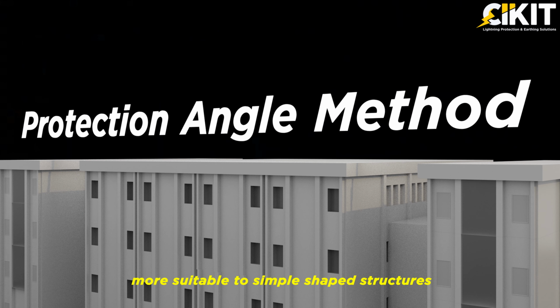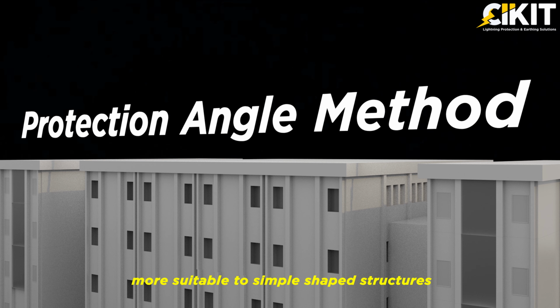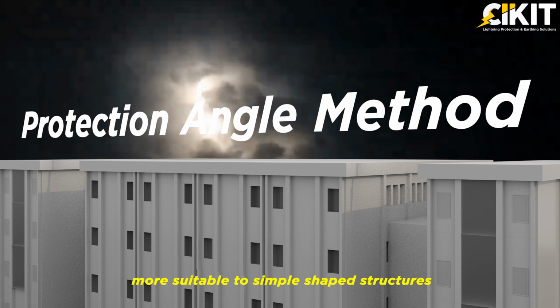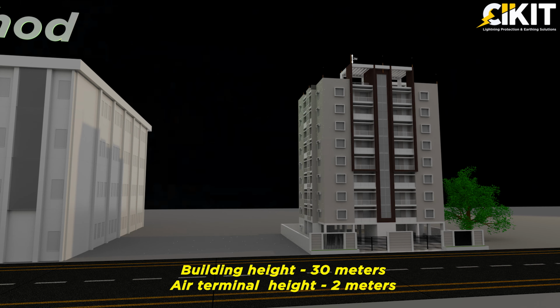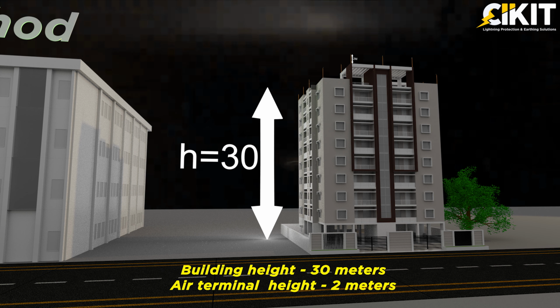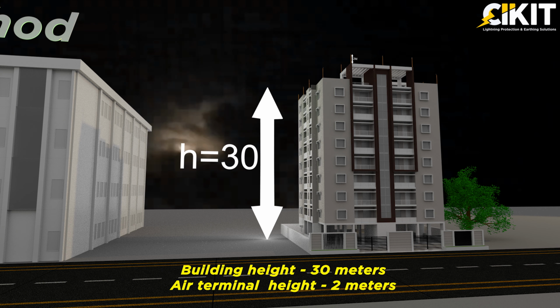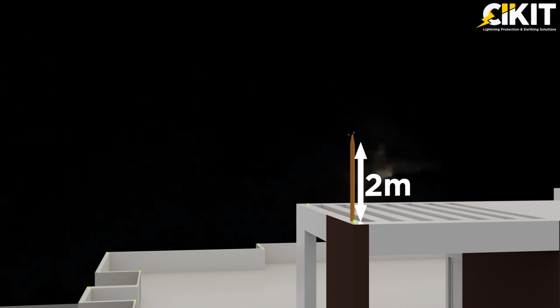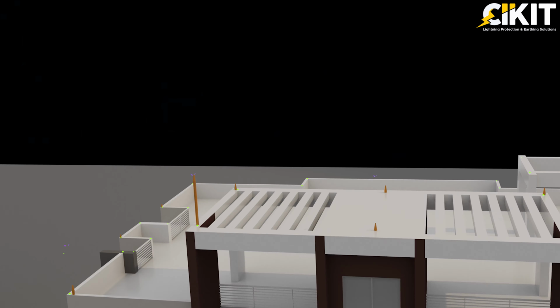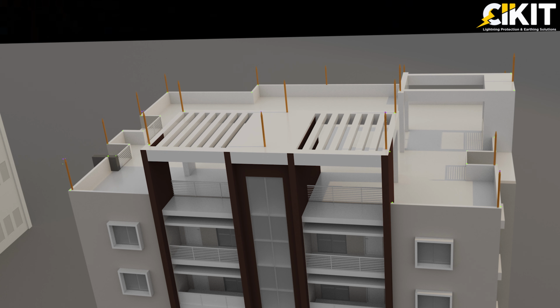In the protection angle method, the angle of protection depends on the height of the air terminal and the level of protection considered for that structure. Let us consider a building of height 30 meters on which an air terminal of height 2 meters is installed at the top, and we are considering level 4 protection as per IEC 62305 Part 3.